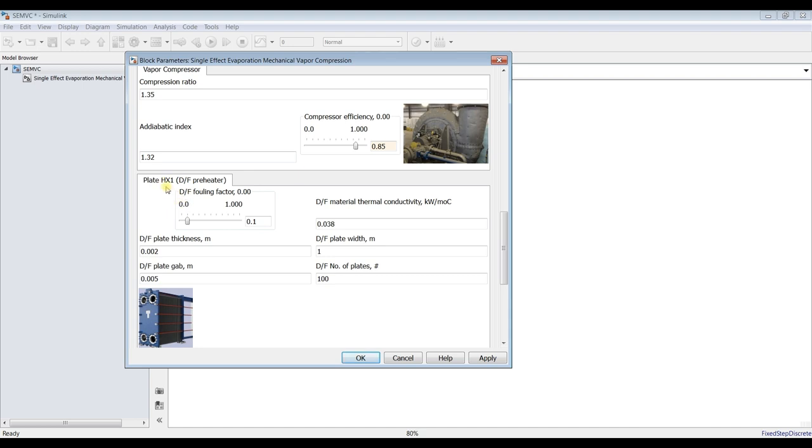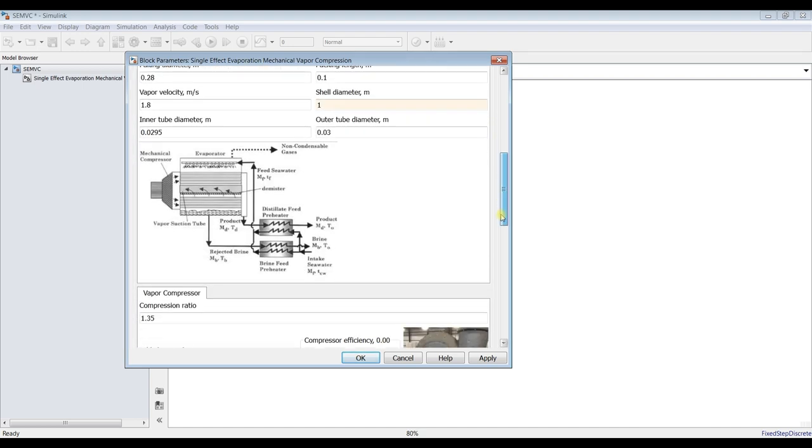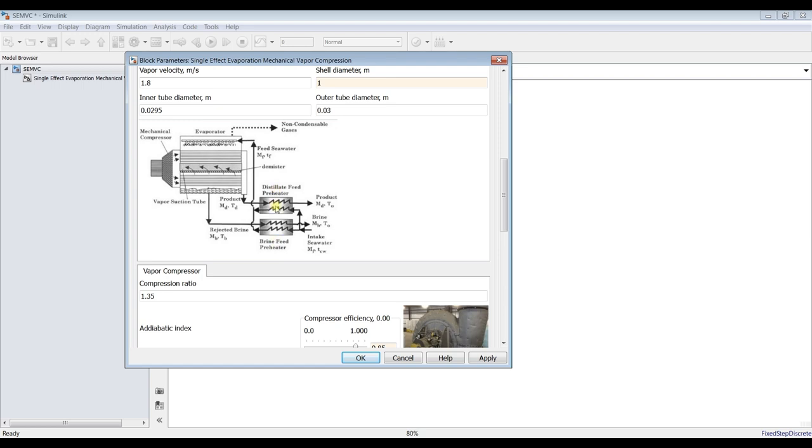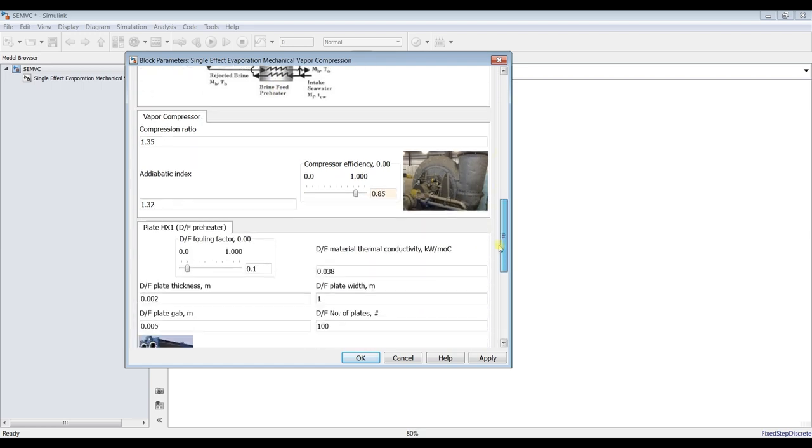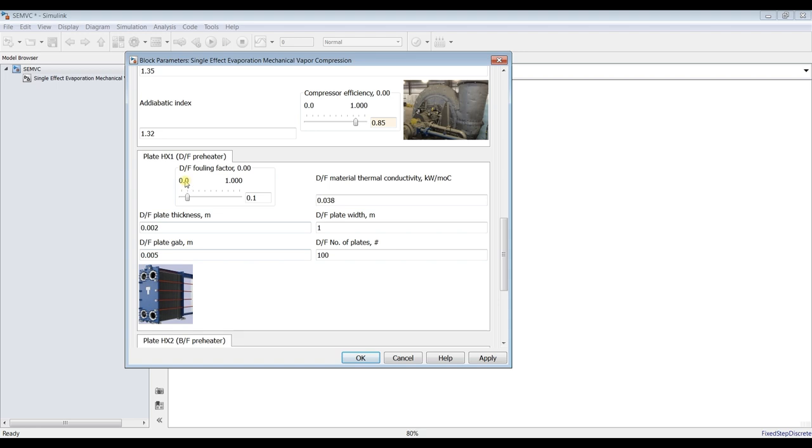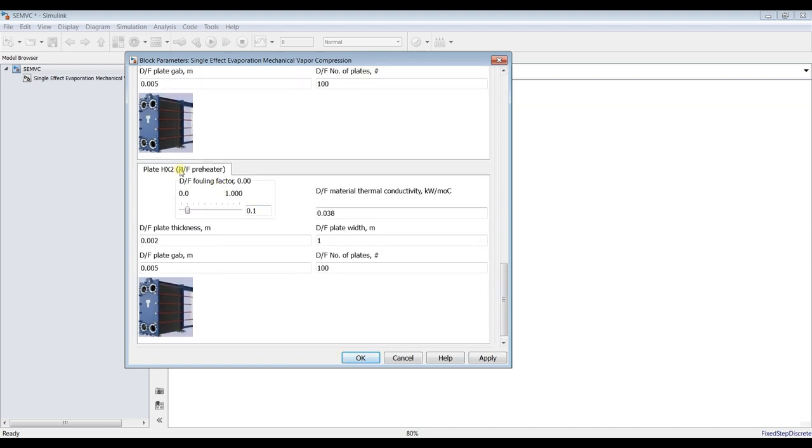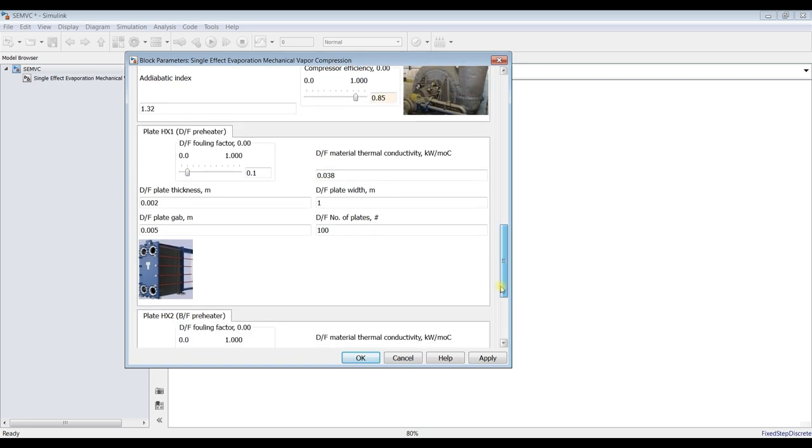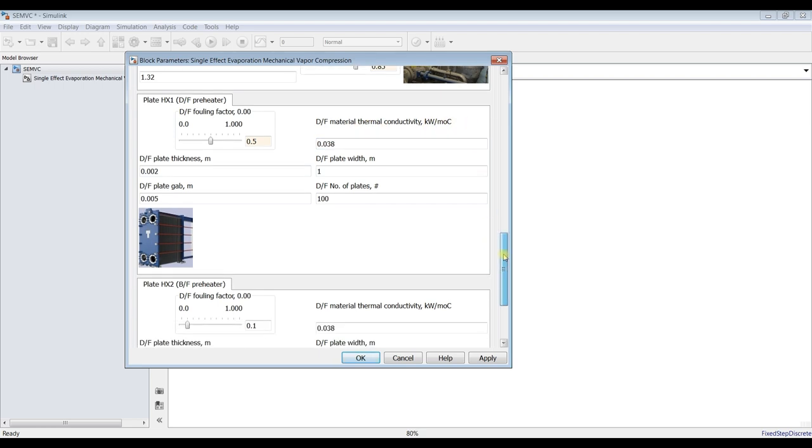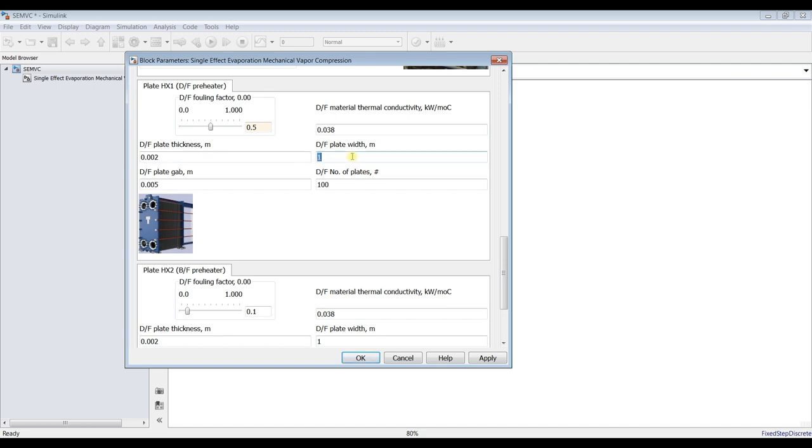We have these pre-heaters are plate heat exchangers, plates, normal plates. So we have to assign some design aspects. For example, for instance, this is distillate feed heat exchanger plate, and this one is brine feed preheater heat exchanger plate. For distillate fouling factor, you can adjust this one. I suppose it's 0.5. Thermal conductivity of the material of each plate, it's up to you as a designer. But this is in kilowatt per meter Celsius. Plate thickness, plate width, how many meters, gap between each plate, number of plates. You can control number of plates, suppose it's 100.